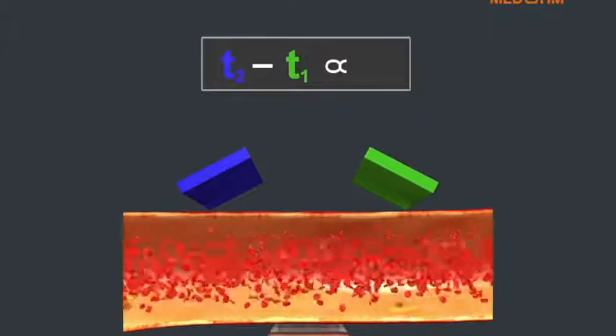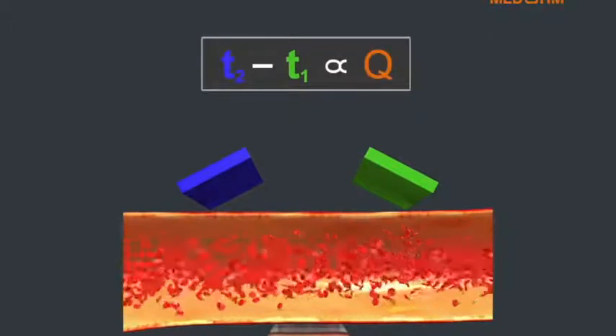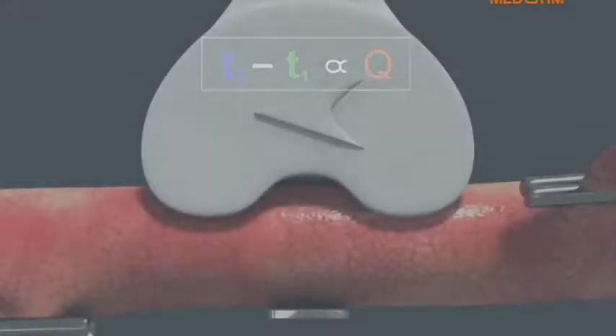The difference in transit time is recorded by the system and is directly proportional to the amount of blood flowing through the measurement area.